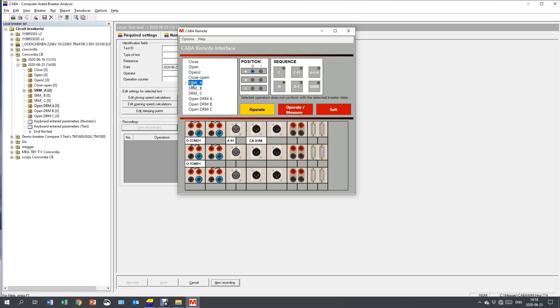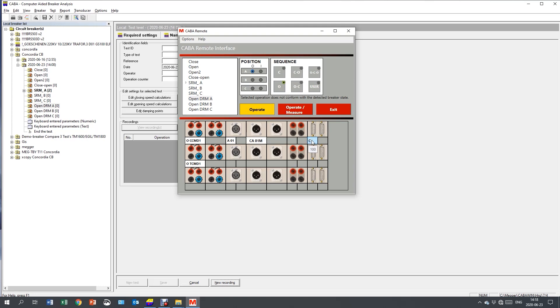I've done my static resistance measurement. And now I want to continue with my dynamic resistance measurement. I select the DRM. And I double click on the motion channel. And I use relative, so I don't have to select the transducer. But still I need to double click. After that, I'm prepared to turn the knob and do the measurement.